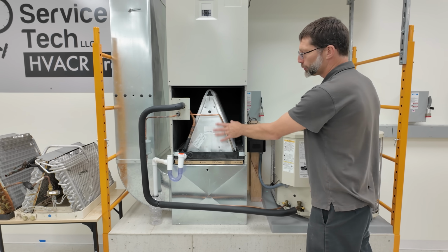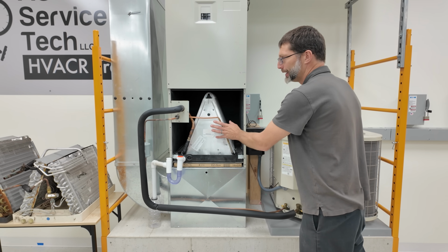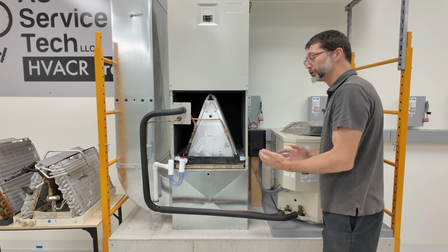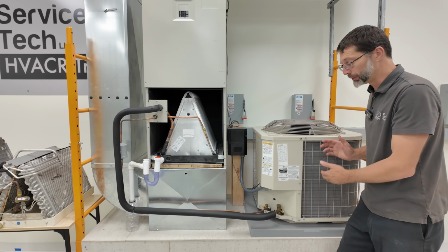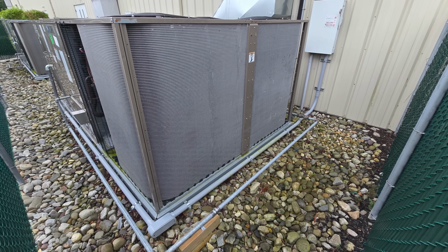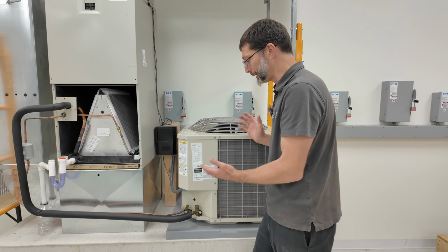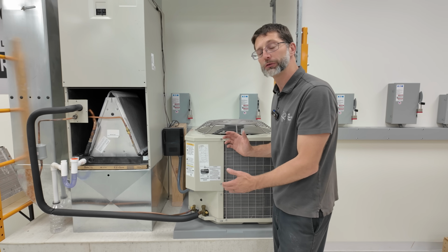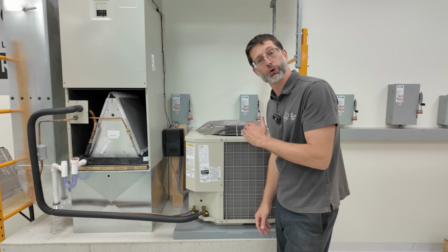And so the indoor coils are not necessarily as prone to corrosion as the outdoor coils. So an outdoor microchannel coil, you want to maybe not install that if you're near the shore, just due to the salt air. You end up having leaks from those. But inland, microchannel coils are fine.